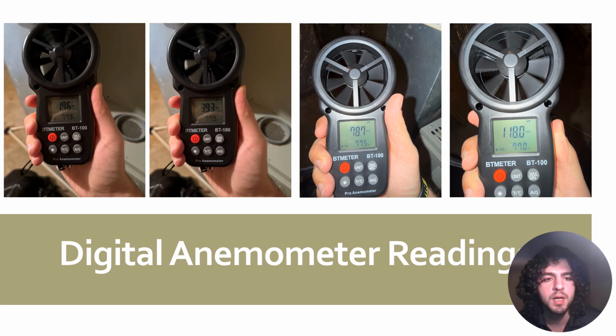For this slide, you could see I used the BT100 digital anemometer, and for this I wanted to test the duct speed. There are 4 pictures from left to right, test 1 to test 4. I decided to take scans of how far I was from the duct, and I noticed that the farther I was, the lower the speed was, and the closer I got, the faster the speed. As you can see, picture 4 shows 118 feet per minute.